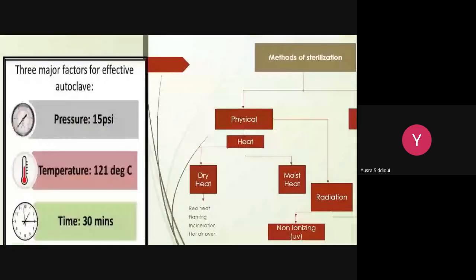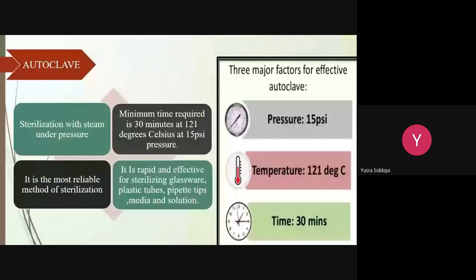Now we move on to the autoclave. The autoclave is a type of moist heat sterilization technique, done with steam under pressure. The minimum time required is 30 minutes at 121 degrees Celsius at 15 psi pressure. It is the most reliable method of sterilization, rapid and effective for sterilizing glassware, plastic tubes, media, pipette tips, solutions, etc.